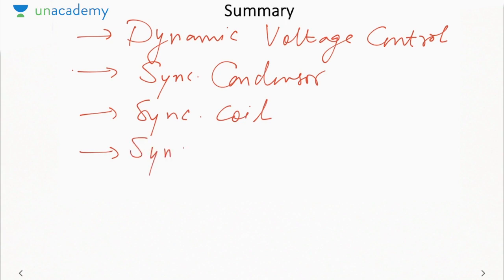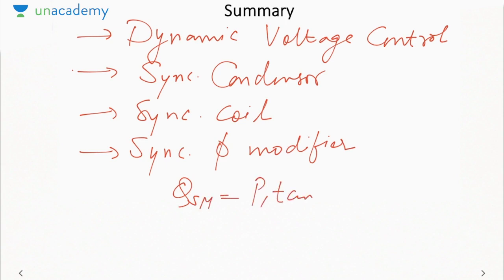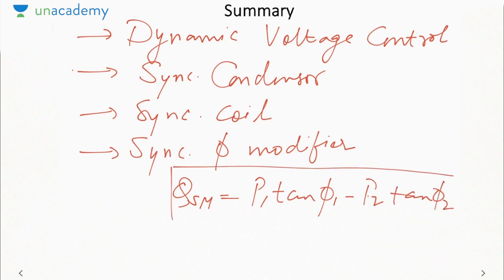Then we saw synchronous phase modifier. It is a synchronous motor at overexcited condition but running at load. Okay, so here we saw Q synchronous motor will be P1 tan phi 1 minus P2 tan phi 2. This is the most important formula from this dynamic voltage control, that is for power factor correction. In the next lecture, we will see some problems based on the voltage control technique.